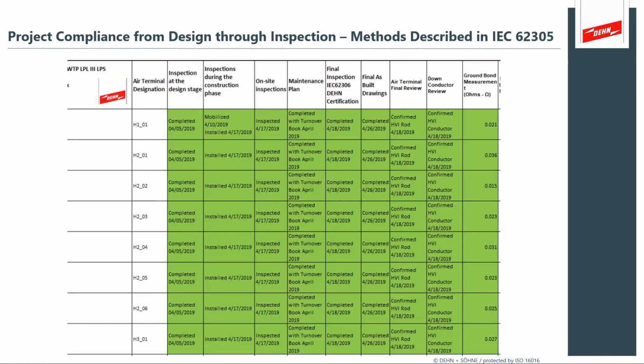In our projects, we take a very careful look at the project compliance and quality control. It's directly built into the IEC standard. It allows us to do quality control and project management and project compliance from the very early design stage through the installation and then final inspection. And then what we can offer the customer is those ground bond measurements to show that the lightning protection system is actually properly installed and that it will give them the coverage that they need for these high value assets.